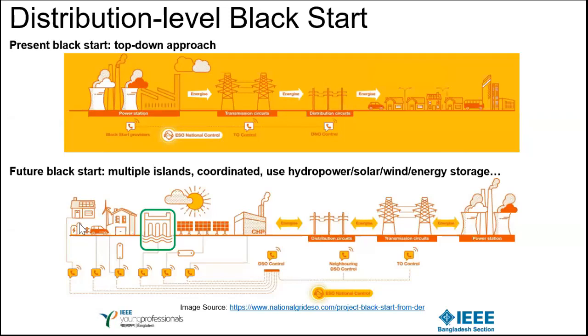At first, they make sure they are operating at 50 hertz frequency, and they start to re-energize the portion of the transmission grid so that the rest of the smaller power plants see that the transmission is energized, at 50 hertz, and then synchronize to the grid. Gradually, once those grids are energized, they interconnect with the distribution utility. Finally, when the distribution utility sees it has the rated voltage, the frequency is running, and there is sufficient generation capacity online, it starts reconnecting individual electric loads. So it's more like a left to right approach in the top figure. That's the traditional view of black start.